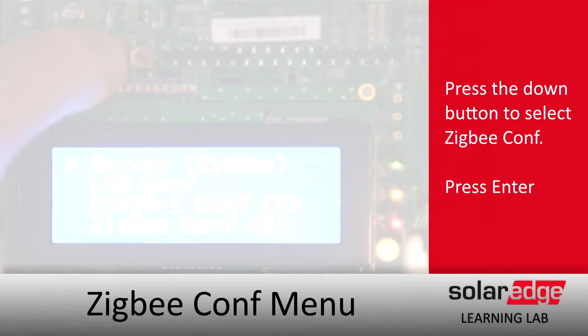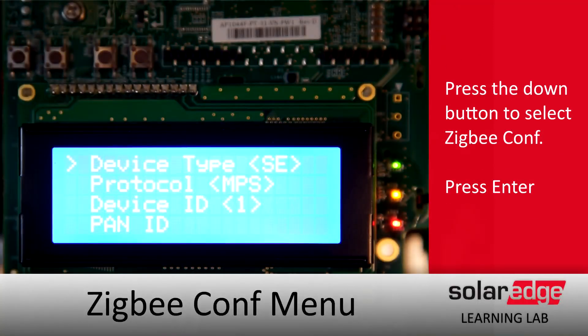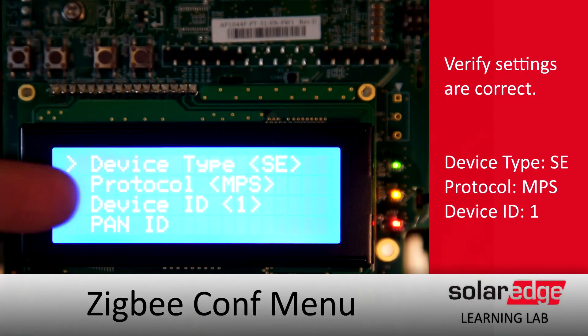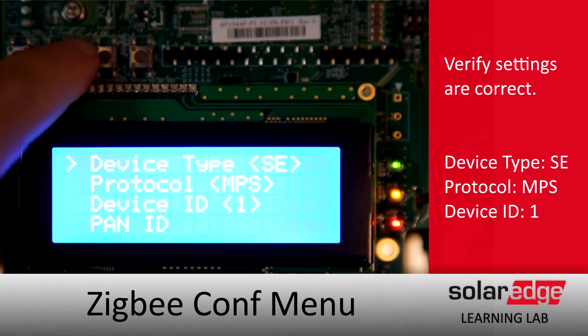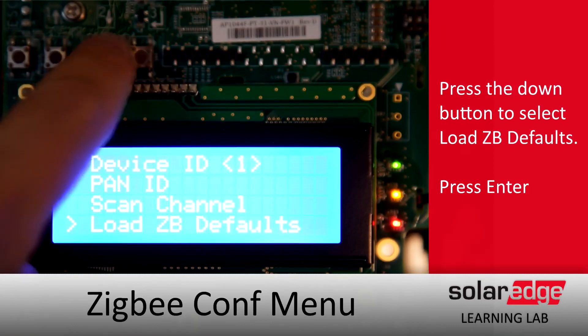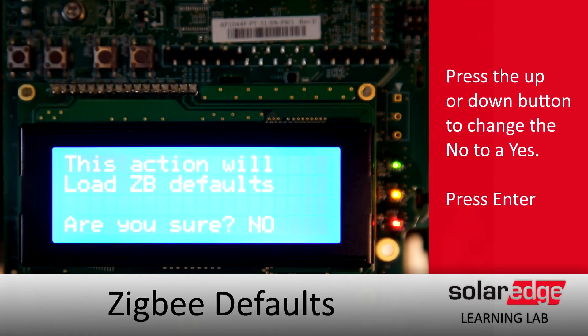After that we'll stay in the communications menu and check out the ZigBee config. We should be set to protocol MPS, device ID 1. The other thing that we'll check, especially if we're pairing up a new gateway, is the load ZigBee defaults. This will help us clear out any old PAN IDs that may be in the memory. To change the no, use either the up or down arrows and hit enter.